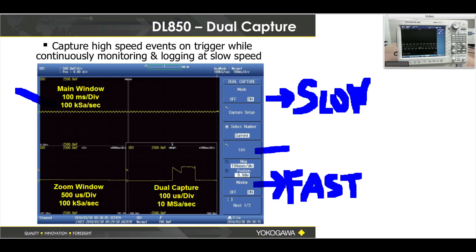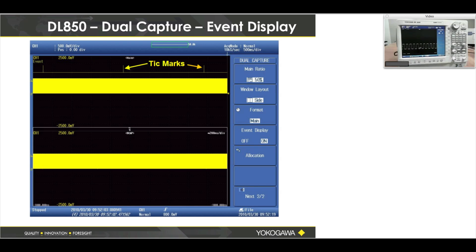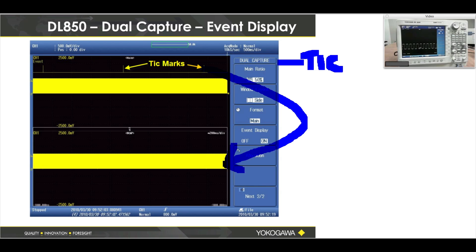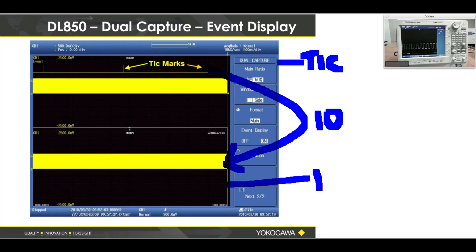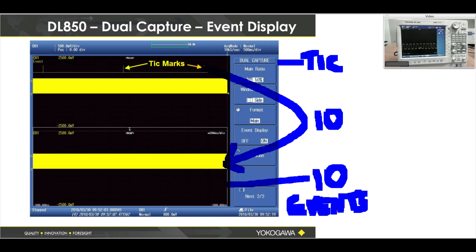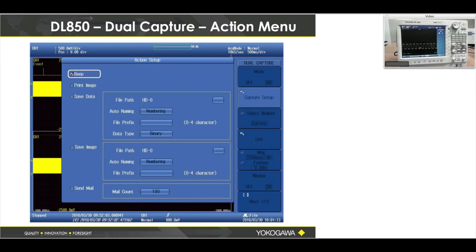Every time my trigger condition is met, I get tick marks in the upper waveform area, and that is an event — it may mean a surge. For each tick mark there's one acquisition, so if I have ten tick marks I may have ten acquisitions. At that point I would have a total of eleven waveforms — one main waveform up here and ten more down here. They're all in one file, so it's pretty powerful.